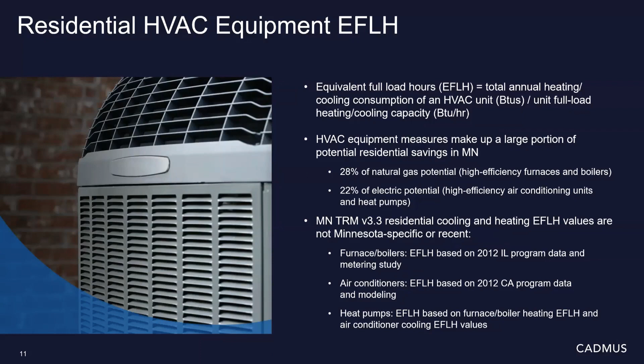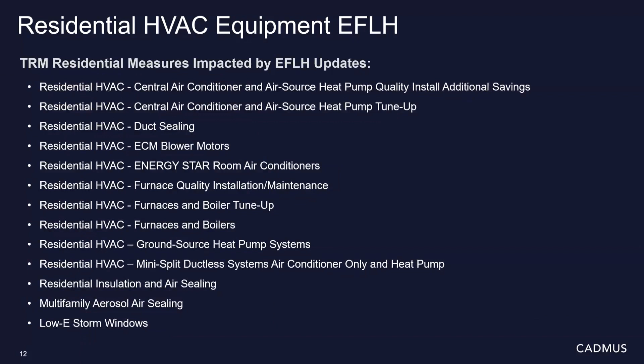However, again, the Minnesota TRM version 3.3 residential cooling and heating EFLH values are not Minnesota specific or recent. For furnaces and boilers, the EFLH in the TRM is based on a 2012 Illinois metering study and program data. For air conditioners, the EFLH is based on a 2012 California program data and modeling. And for heat pumps, the EFLH is based on furnace and boiler heating EFLH and air conditioner cooling EFLH values. But we know that heat pumps operate quite differently from furnaces and boilers. So while updated thermostat savings only apply to one TRM measure, the updated residential HVAC equipment EFLH values may apply to 13 existing measures, all listed here, which reference heating and cooling EFLH values in their algorithms.